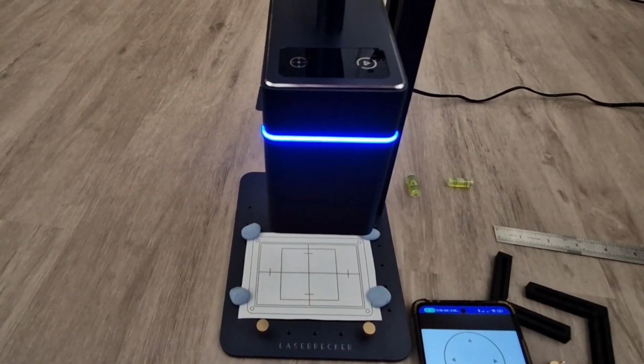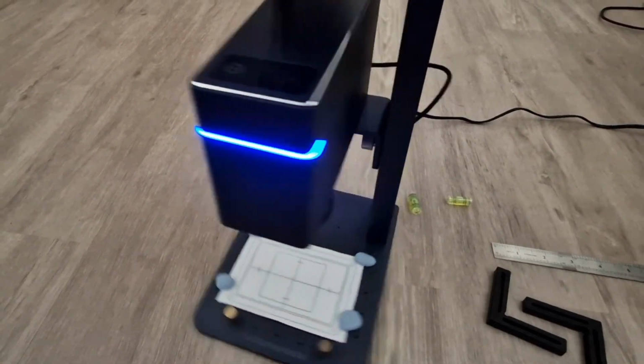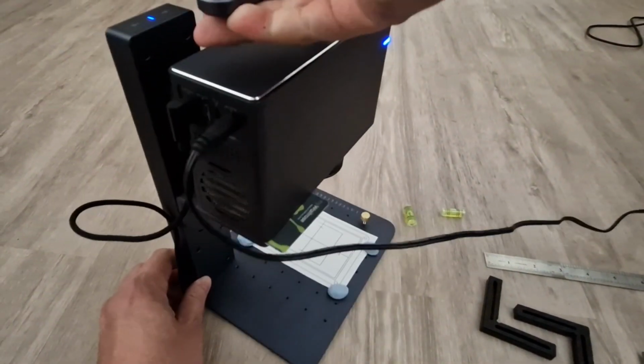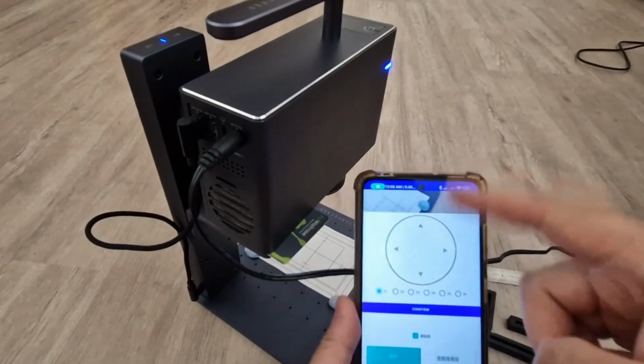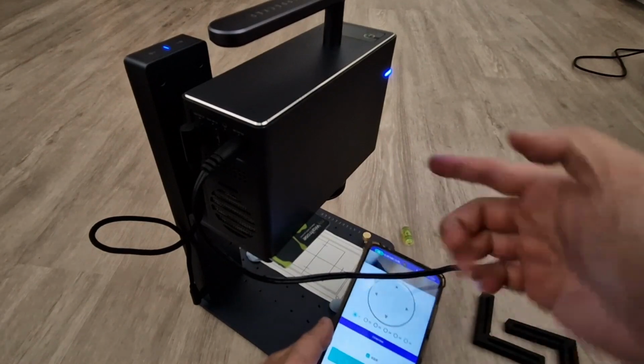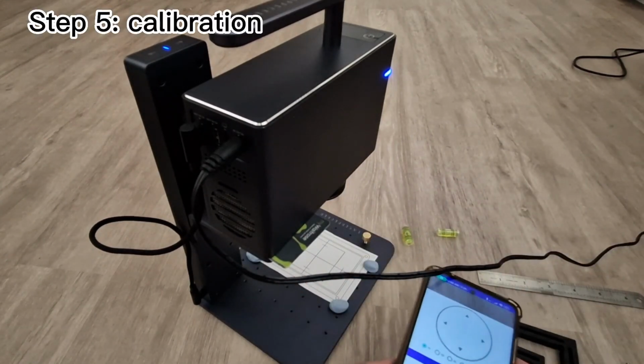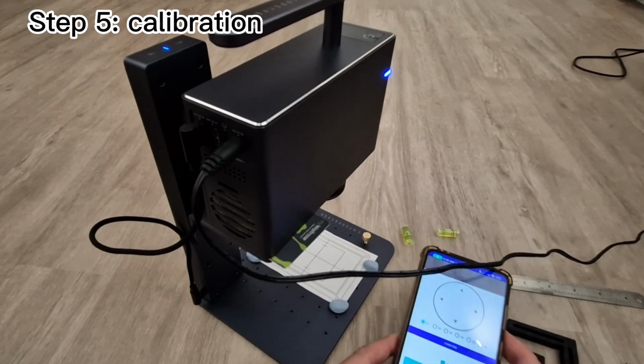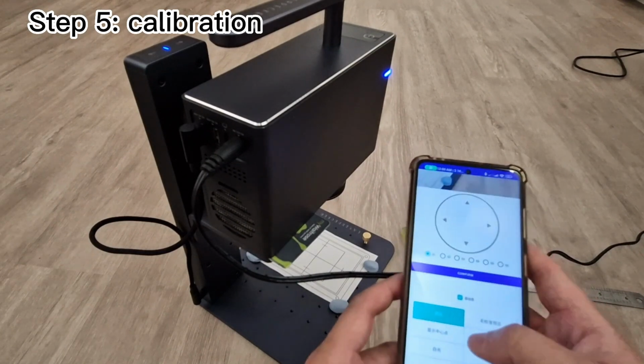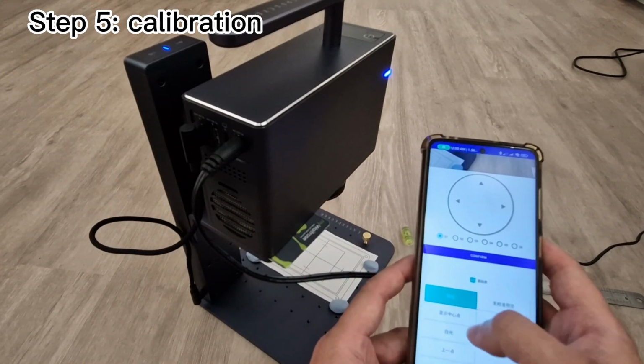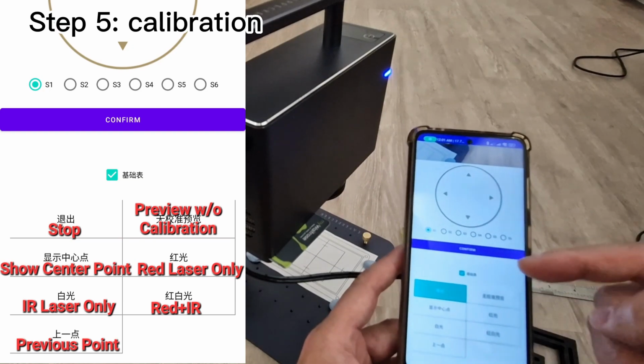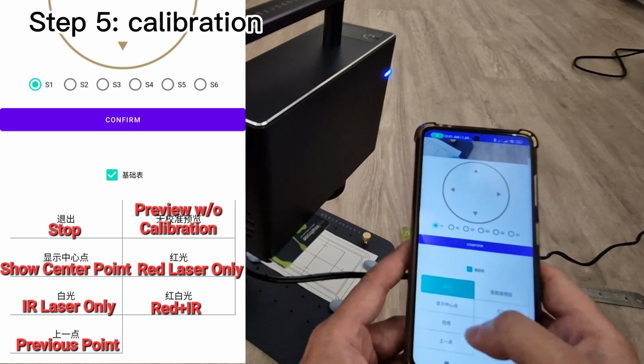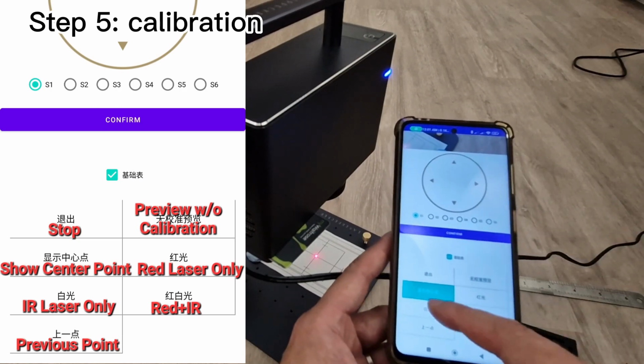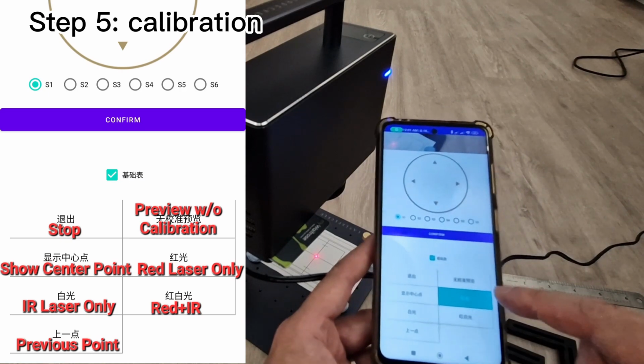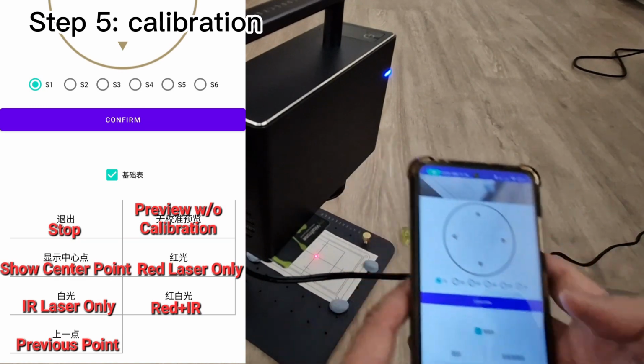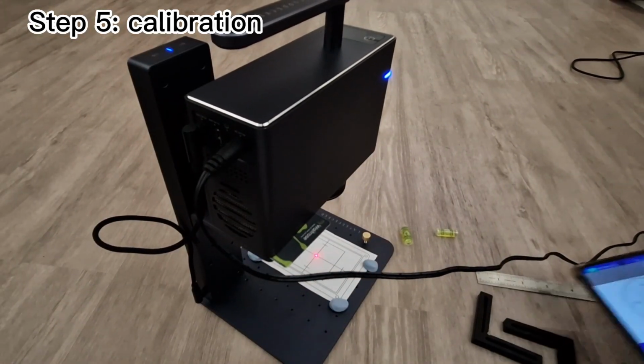Before we start calibration, let's turn the laser around 180 degrees so that when we use these up, down, left, right controls, we are in the right orientation with the movement. And okay, I think we can start. Again, let's press this button to show the center point, and by default it's going to trigger both red and infrared lasers. We don't need the infrared part, so show center point, and then quickly we switch over to red light only. And now we begin the actual calibration.